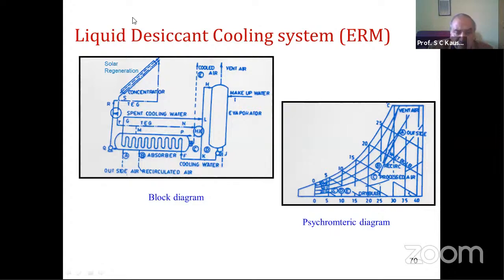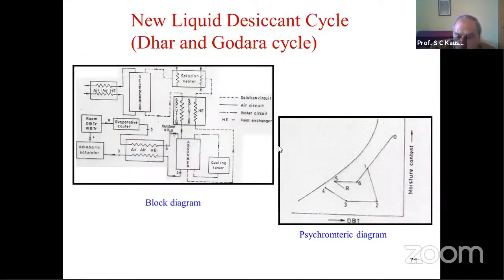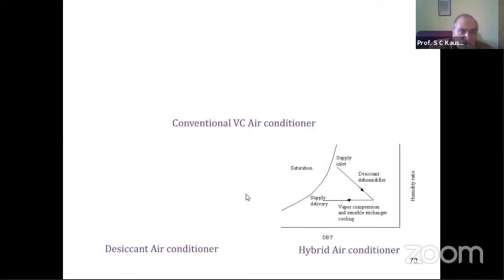Now in the desiccant system, we do the cooling through the vapor compression system, and then it is supplied. It is a simple option. So hybrid air conditioning is desirable. These charts are shown on page 73. Now this is the hybrid basic cooling cycle. So the space which is being cooled, and then a combination of a dehumidifier, and this condenser and evaporator and this compressor. So by following the process of sensible cooling through the vapor compression system, and this is the solid desiccant cooling system, as you can see from different state points shown on this diagram. So this is the solid desiccant hybrid space conditioning option, with simple operation, a lot of energy saving can be achieved, and overall COP is higher for the hybrid air conditioning.